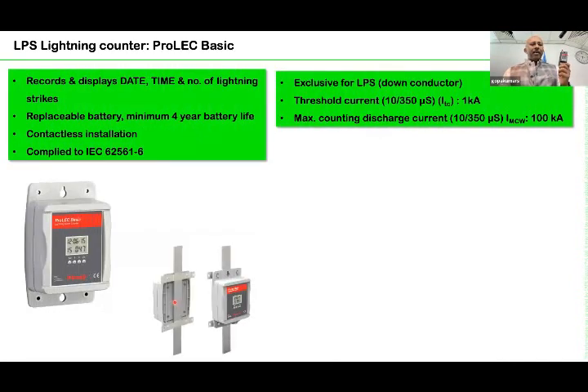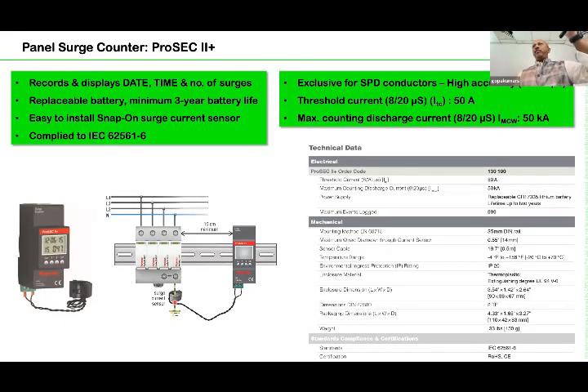Similarly, the lightning counter, I'm sure you are aware, this is not a surge counter. This is, of course, also a current counter, but it has to be used on the external down conductor. External down conductor means you have a lightning protection system, and on its external down conductor you can use it, whereas the previous one which I have shown is for the panel board.